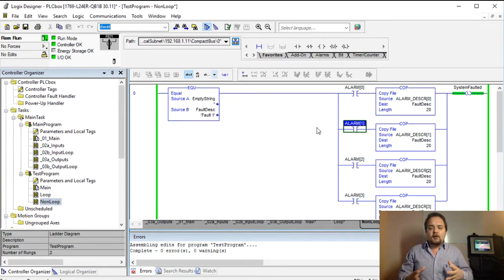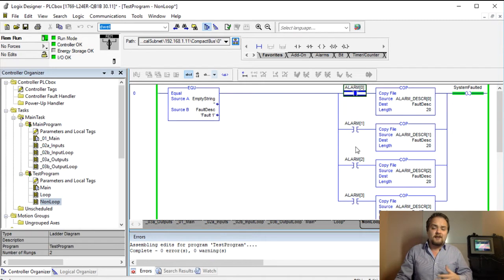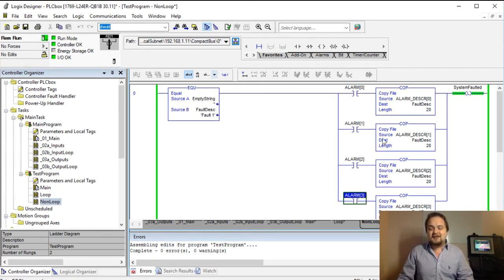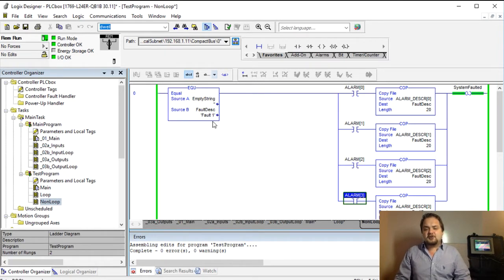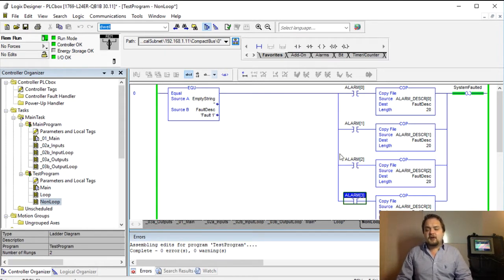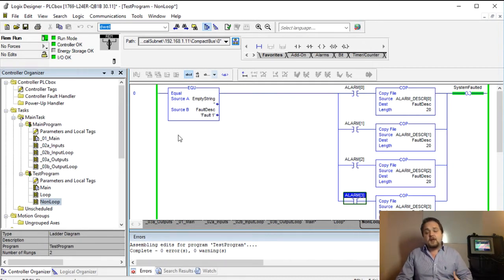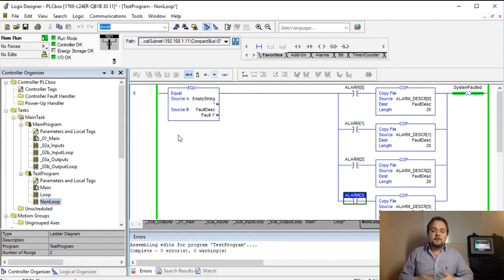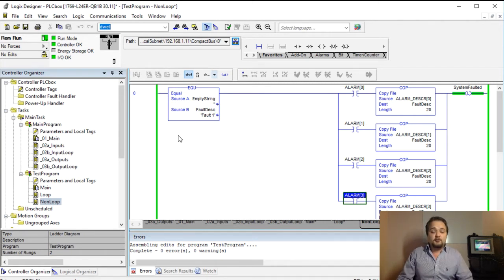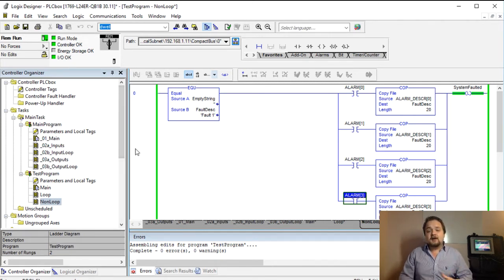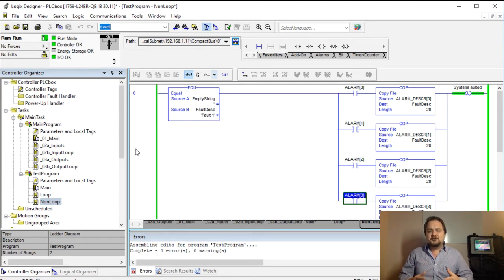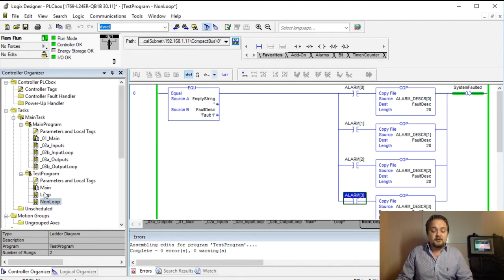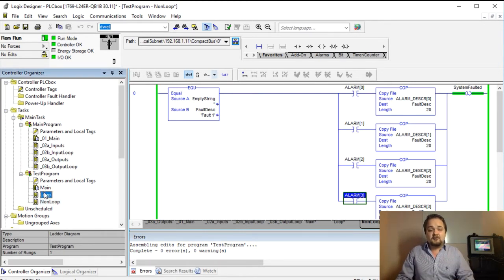But I want you to be aware that this is very, you only have four alarms here if you wanted to implement like I said a thousand you would have to essentially copy paste this rung you'd need to make sure that you have this under some kind of a structure. So this would be extremely troublesome. So this is where a loop comes in so whenever you have a repeating structures you can always or almost always replace them with a loop and in most situations this becomes more efficient if you have rungs which start to kind of go over the screen and it's just becoming very troublesome or time consuming to implement.